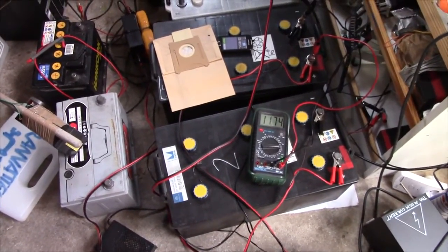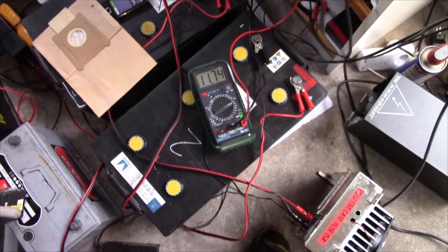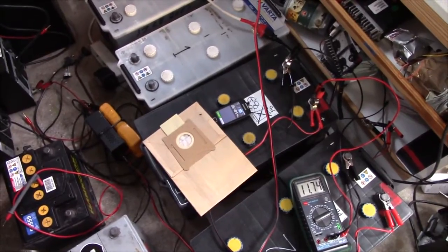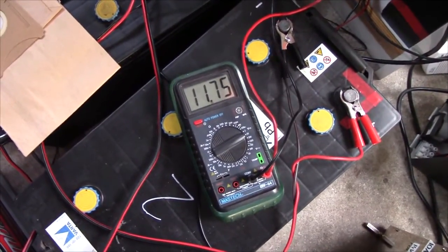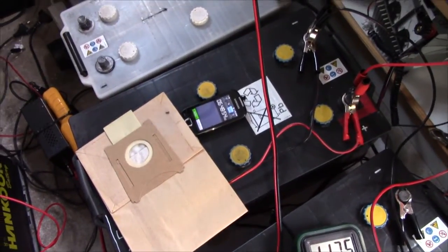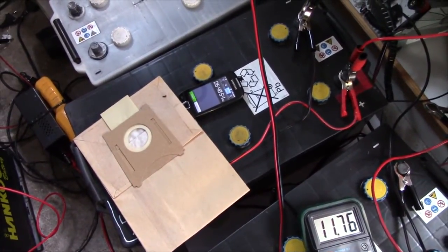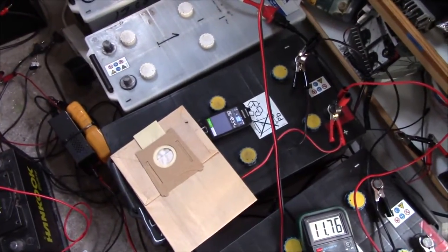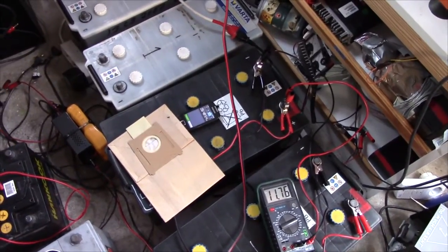It looks nasty and it's not like I couldn't do without it. But we're going to have to try and cycle this other one and see if the equalization charging cycle made it any better. In the meantime, I'm going to recharge and equalize this one. If we look at the open circuit voltage, it's already back to almost 11.8 volts. This battery isn't really too deeply discharged, it's just got a very high internal resistance, perhaps due to sulfate. With a bit of luck, maybe another cycle, good equalization charge could do some good. Maybe get it back up to at least 80 amp hours.